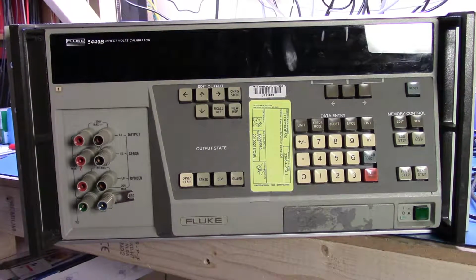The reason I bought this is that I took my 5440B and dropped it off to Fluke calibration to have them give it a solid calibration, because calibrating that unit along with my Hewlett-Packard 3458A enables me to calibrate my Fluke 5200A AC calibrator, giving me a set of AC and DC calibration standards I can use here in my home lab.